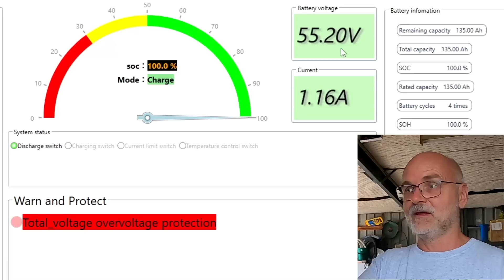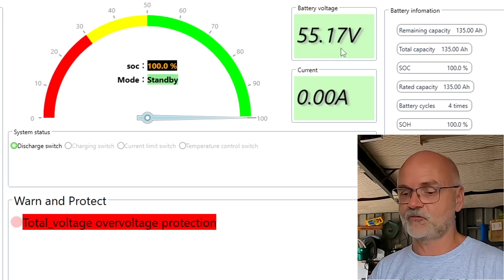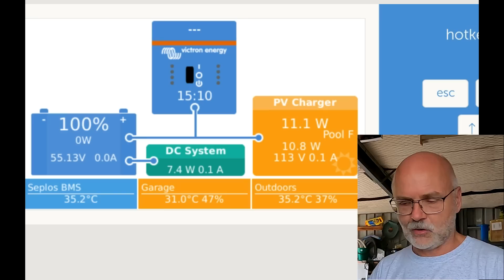So we are charging the slave but not the master, right? It could be the other way around at some stage. So now the slave has turned off as well. We reached 55.2, and we can see the solar charge controller throttles down now to 10 watts, 5 watts, and it will turn off altogether in a minute. So now both batteries are getting discharged very slowly.